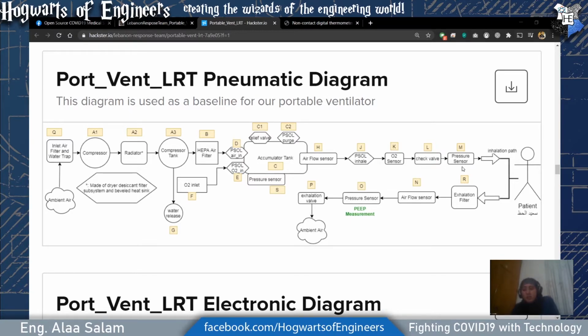Okay, so moving back into the pneumatic diagram, we reached pressure sensor M. So pressure sensor M to H, the flow sensor, this line, we call it the inhalation line. This is the line where the patient takes the breath or the ventilator gives the breath to the patient. Right. We gave the patient the breath. What do you do now? Just hold it in? No, you need to release it. So you need to put it back into the circuit, but pay attention.